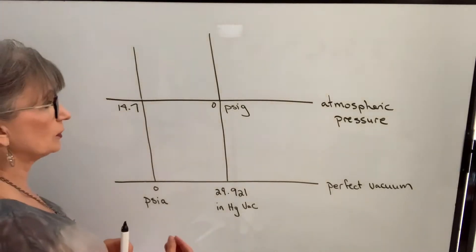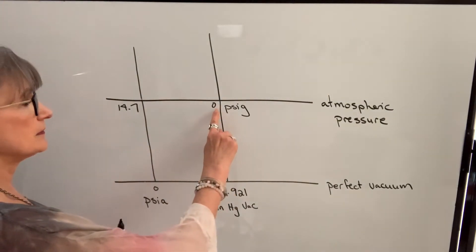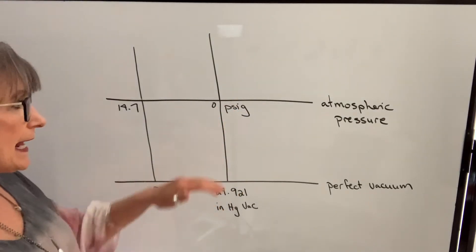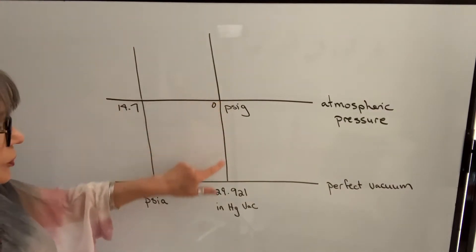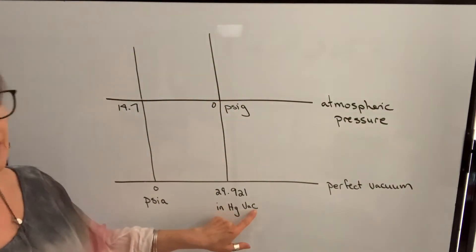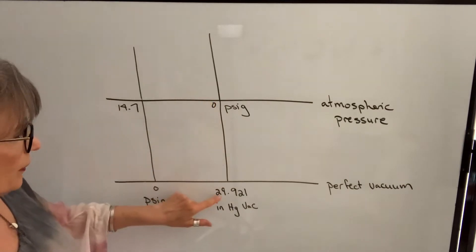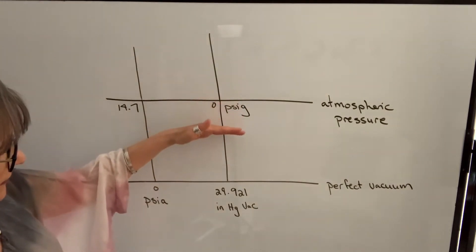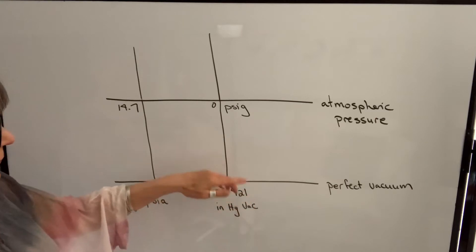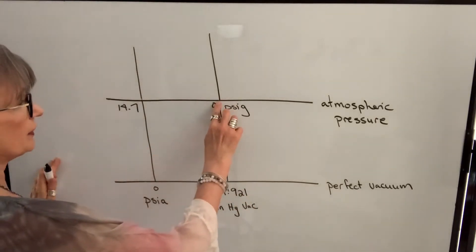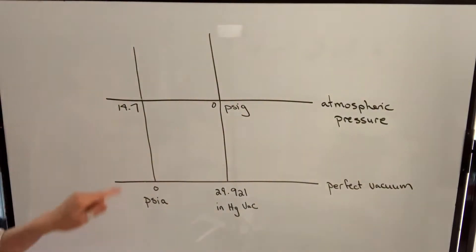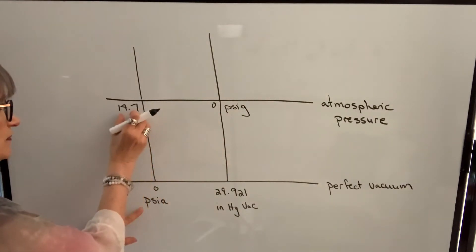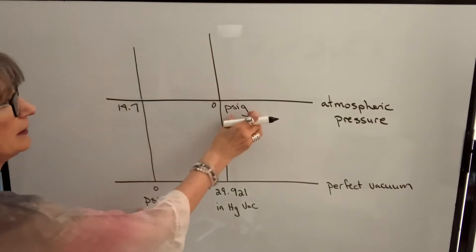If we look at a gauge, PSIG starts at zero at atmospheric pressure. Anything less than atmospheric pressure will measure as inches mercury vacuum, going from zero to 29.921 as pressure decreases or vacuum increases. So our numbers go from zero to 29.921 on the vacuum scale, while PSIG starts at zero and continues upward.